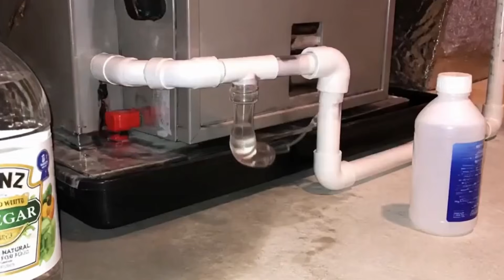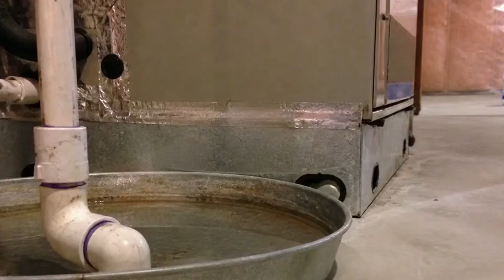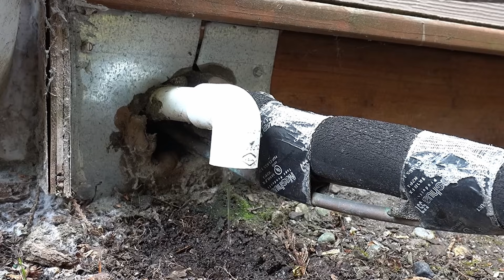If you insist on using both, the guidance is to dose with peroxide, wait 10 minutes, flush completely with water, and only then use vinegar. That water flush is the entire safety margin. And never use bleach in your system, it eats the cement in your PVC joints and corrodes metal drain pans, which is the exact repair you were trying to avoid in the first place.